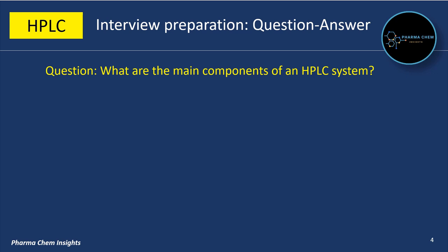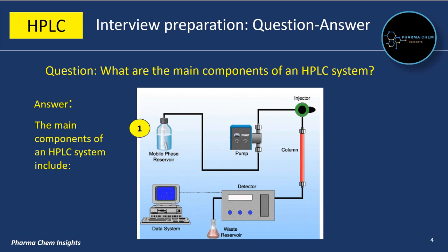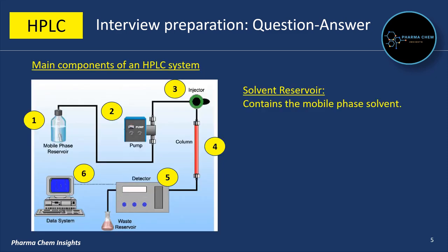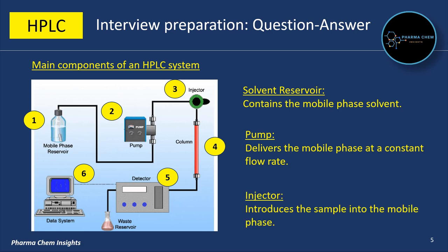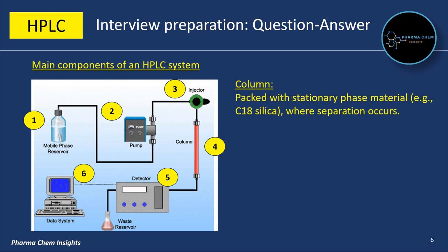Next question: what are the main components of an HPLC system? The main components include — as you can see in this diagram — mobile phase reservoir, pump, injector, column, detector, and data system. The solvent reservoir, also called the mobile phase reservoir, is a glass bottle that contains the mobile phase. The pump delivers the mobile phase at a constant flow rate. The injector introduces the sample into the mobile phase.